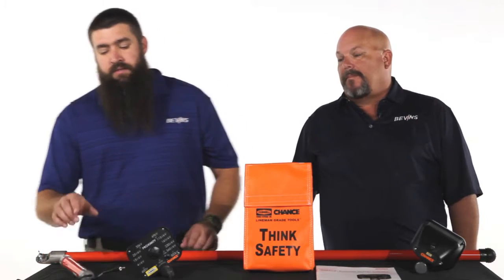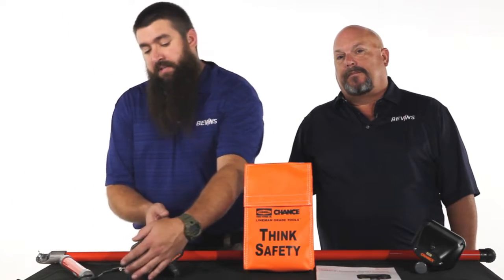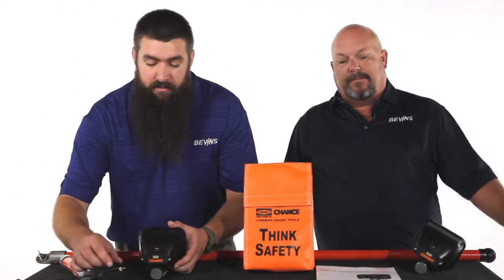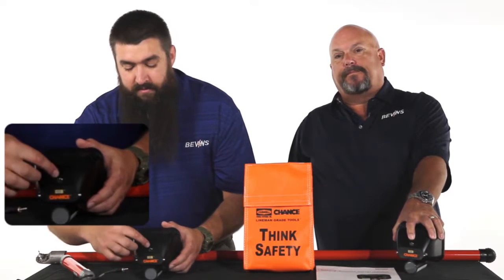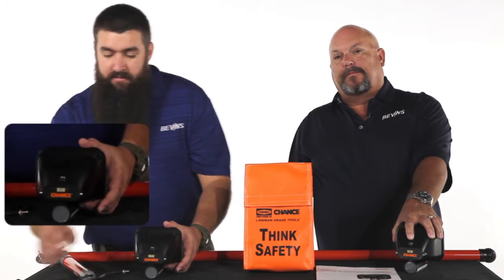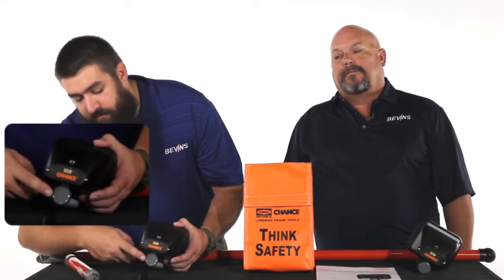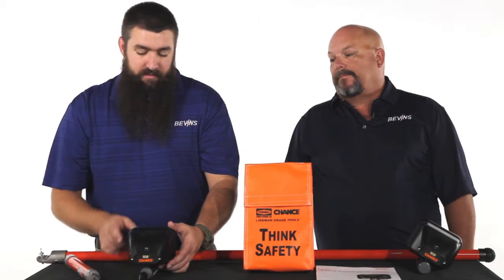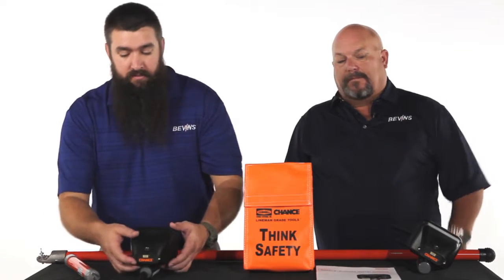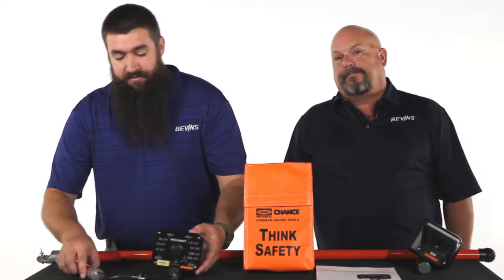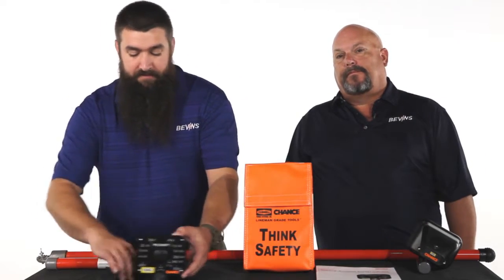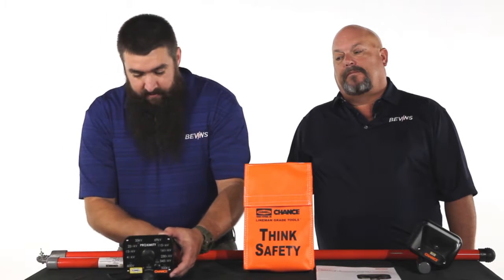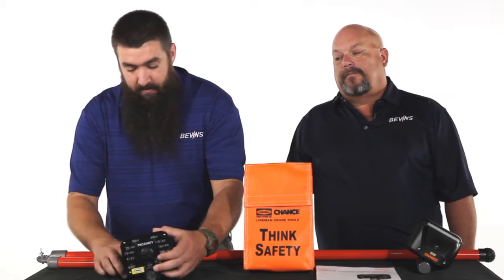So to use the field tester, we basically will need to plug the connector from the tester into the jack on the proximity unit, and then we'll take the clip from the tester and set it against the input sensor of the proximity unit, and this will cause it to basically simulate a reading. And we'll see on the front, let me just flip it around here, we'll see voltage on one of the ranges. So I'm going to set this up here and power the unit on.